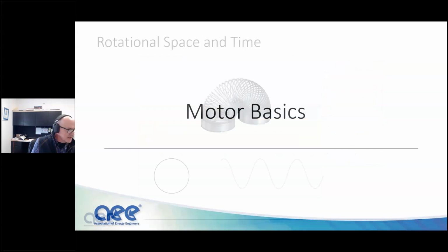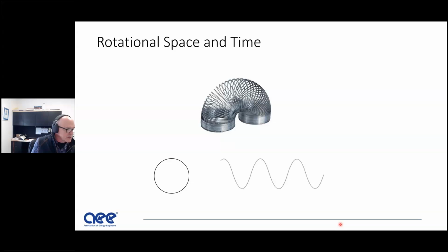Let's start off with the basics here. I always like to describe rotational space and time using an old slinky. If we close up the slinky and turn it one way, we see a perfect circle. If we turn it the other way and expand it, we see a perfect sine wave. This is the way motors like to operate, because power is delivered as a sine wave and it rotates the motor perfectly. When that sine wave isn't perfect, the rotation isn't perfect. The motor is of course held tight by the bearings, but it is not operating efficiently and it's generating heat because it's not a sine wave. So a sine wave is ideal.